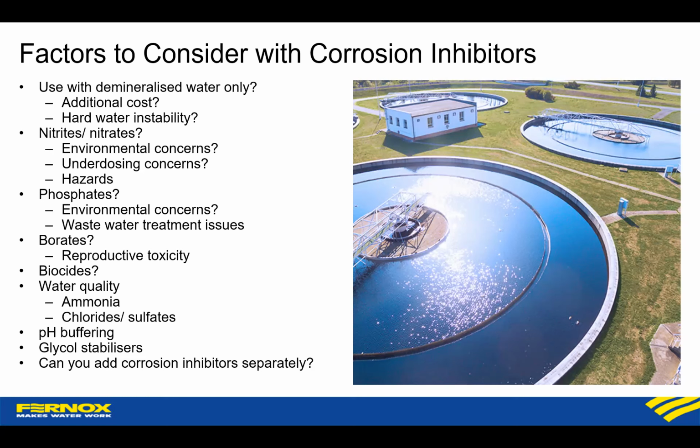Water quality, so similar in some ways to the first point about do you need demineralized water, what sort of water can you put with this product. You might get some products which say can only be used with a max of 100 ppm chlorides, for instance, so something to bear in mind.